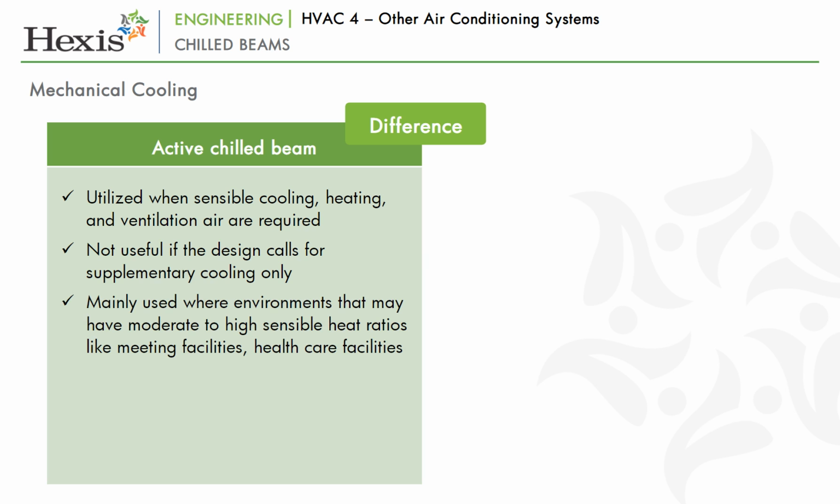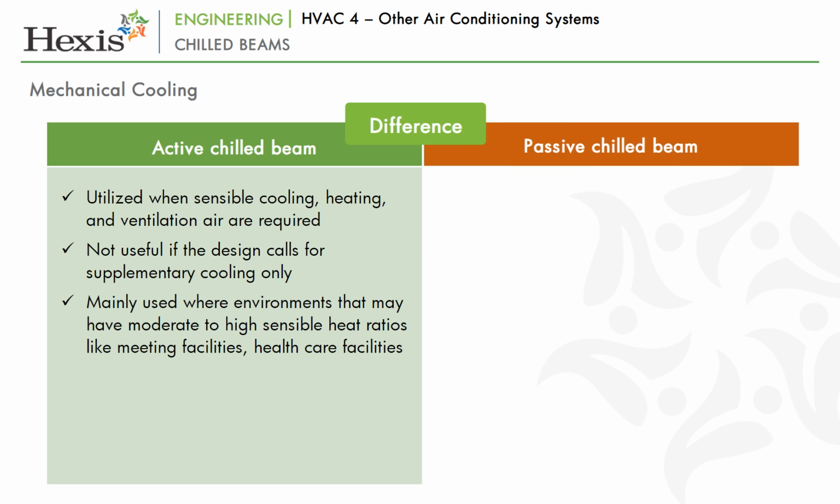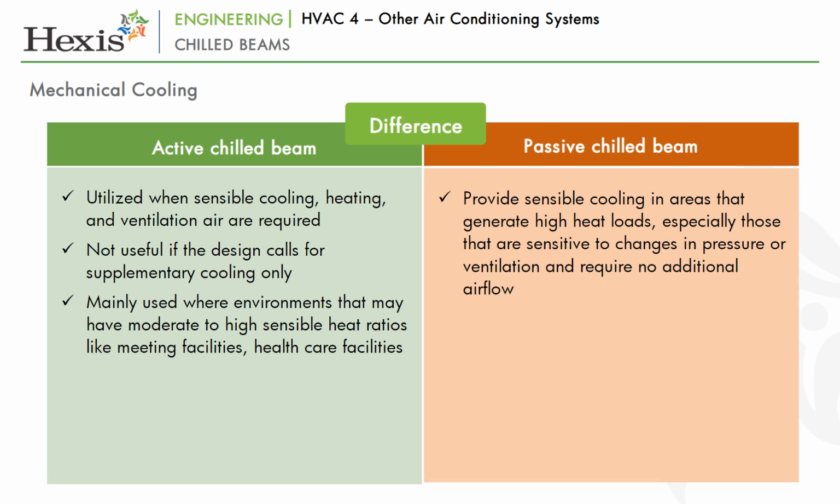Classrooms, private and public office buildings, meeting facilities, healthcare facilities, and other environments that may have moderate to high sensible heat ratios, and building retrofits where space for new mechanical equipment may be limited, are all good applications for active chill beams.